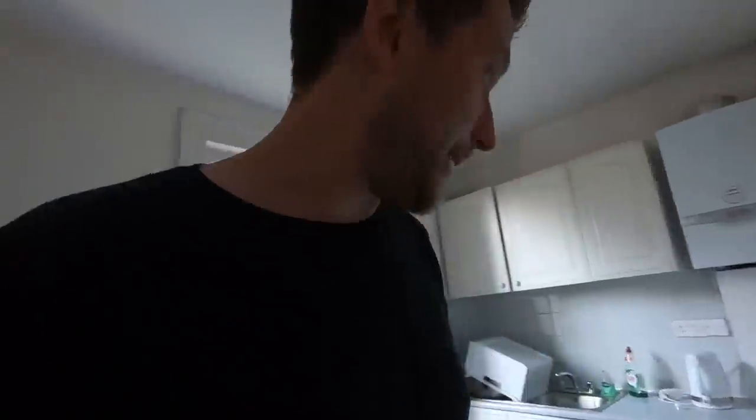What I'm going to do first is go around and unplug everything, because the great thing about rentals is that if they're empty properties, you can just do all your insulation testing without any fear of damaging anything. Because when you're doing the EICR in any normal place, it's very seldom you can do your insulation resistance testing - there's so much stuff plugged in, stuff you can't reach, and you can't do it half the time. I once damaged the PCB on a boiler, which was an expensive repair.